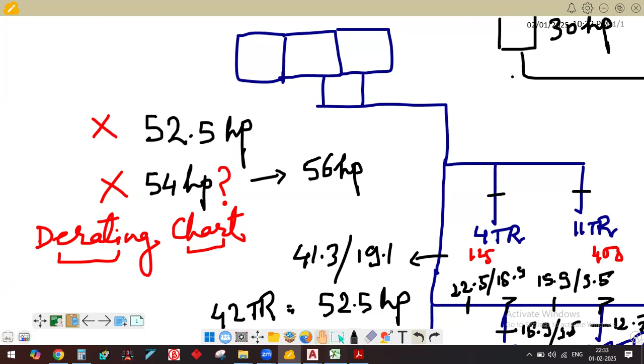The best option is that if you are doing a VRF project now or in future, just connect with the vendor and ask for the derating charts. Take some standard machines, from 12 HP to 50 HP, or the entire range from 10 HP to 20 HP, whatever it is. Every HP unit will have a different derating chart, and different companies will have different charts. Samsung will have different, LG different, Carrier different.